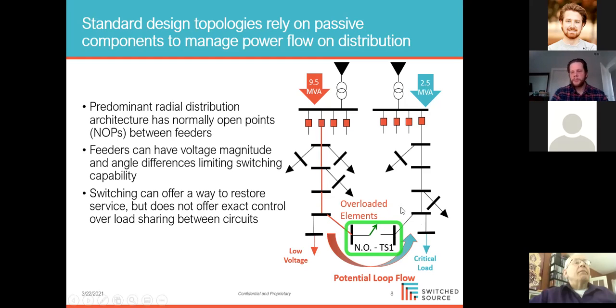When they want to balance load, if there's too much load on this circuit, they'll close this switch and open one upstream, so less load is fed from this circuit and more from down here. Similarly, if there's a power outage, say a tree falls on a line, they'll open a switch to isolate that, then use this normally open point to restore service to customers on the second half of the feeder.